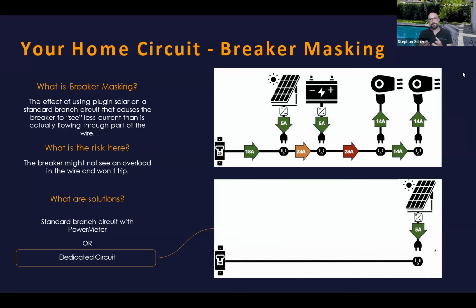And that dedicated circuit simply means you go from a breaker, a single wire, a single circuit essentially, to one outlet. That is not a common occurrence in most homes these days, which is why, for instance, we as a company generally sell our systems with power meters. You can't really ensure that. If you know for sure, absolutely, the NEC says you can run a system on a 20 amp breaker up to 2,400 watts. That then gets reduced again if, excuse me, you're running this longer than 3 hours, you might still degrade the wiring, so you have to reduce it to 80% of those 2,400, which is where we get this strange number, 1,920 watts in some other states, like Colorado, as a maximum system size.